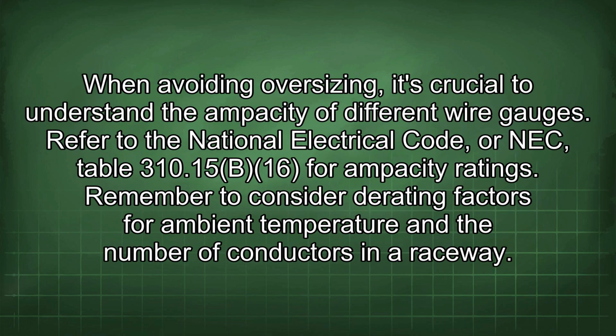When avoiding oversizing, it's crucial to understand the ampacity of different wire gauges. Refer to the National Electrical Code, or NEC, Table 310.15(B)(16) for ampacity ratings, and remember to consider derating factors for ambient temperature and the number of conductors in a raceway.